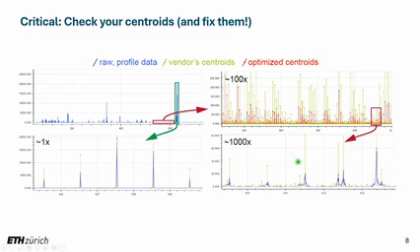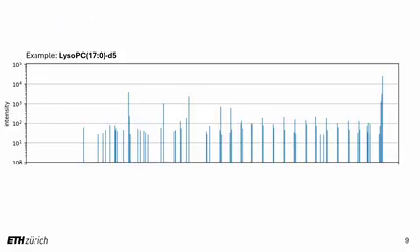We basically had to re-engineer, or redesign to a large extent, the centroiding to get much better results. Put differently, we were using what the vendor provides, through ProteoWizard, and it was not so satisfactory. Then you start looking at why we are not matching these fragments, and it turns out that the centroiding is just not so good down there. So long story short, check the centroiding. I'm not saying everything is wrong, but if you check and double check at least once, you might see that you can improve it, and for us it was a game changer. What I'm going to show you works because of this.